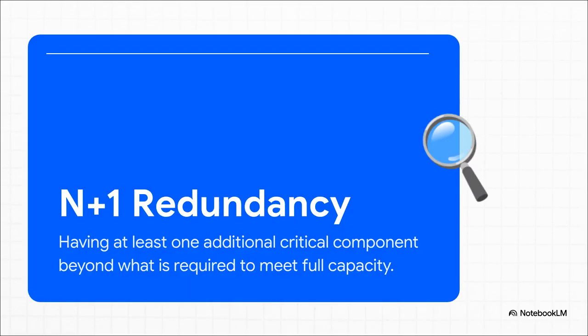This obsession with making things fail-proof has a name: N+1 redundancy. It's simple. N is the number of components you need to run the hospital, say 3 giant chillers to keep it cool. N+1 means you install 4. That way, if one fails, the system doesn't even blink. There's always at least one backup for every critical system, ready to take over instantly.